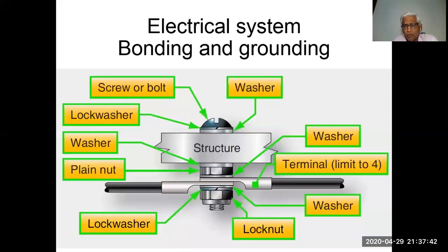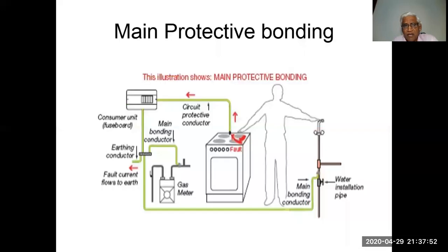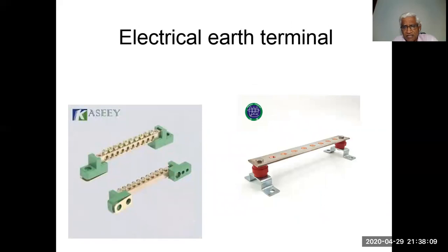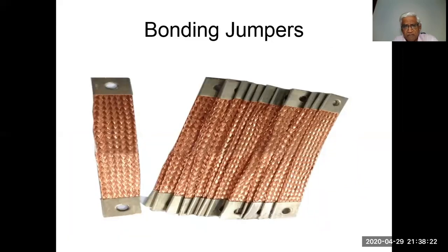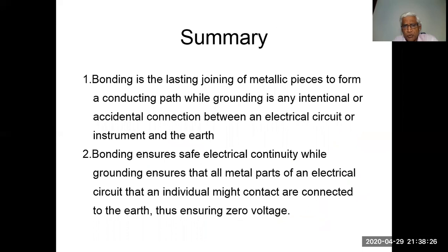Electrical system bonding and grounding: you can see clearly how nicely the job has been completed here. The two conductors are touching each other. And in this, the main protective bonding is such that the body of the supply coming from this side and the water pipeline are at the same potential, so he won't get a shock. And these are the electrical earth terminals provided where a number of connections have to be taken. They can be connected to the incoming and the outgoing. You can increase the number to something like 10. And these are the bonding jumpers. They are flexible ones.